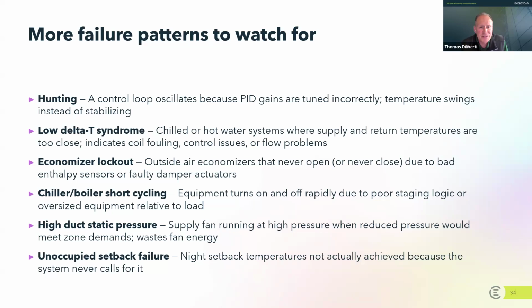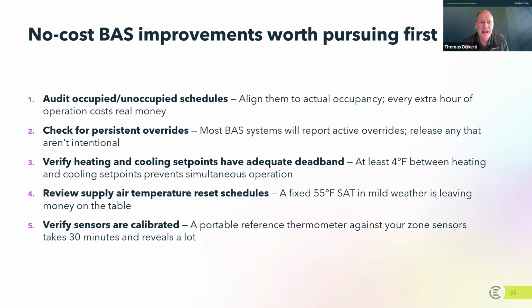This idea of low delta T. So you don't have enough temperature change for your chiller and your boiler systems. I mentioned economizer lockouts, boilers and chillers that are short cycling, so they're turning on and off too quickly. And this is where I think you've got to start. I think you've got to start by checking your schedules, look for those overrides. Again, look for those deadbands. Make sure you're looking at those reset schedules. I had mentioned that earlier a couple times.